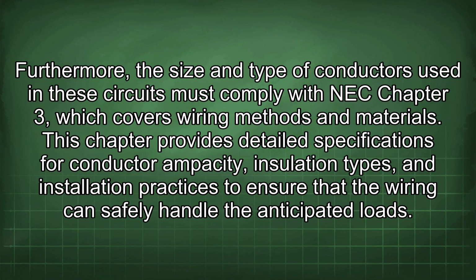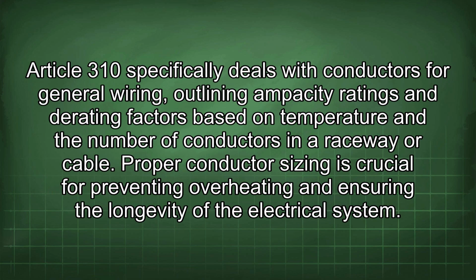This chapter provides detailed specifications for conductor ampacity, insulation types, and installation practices to ensure that the wiring can safely handle the anticipated loads. Article 310 specifically deals with conductors for general wiring, outlining ampacity ratings and derating factors based on temperature and the number of conductors in a raceway or cable. Proper conductor sizing is crucial for preventing overheating and ensuring the longevity of the electrical system.